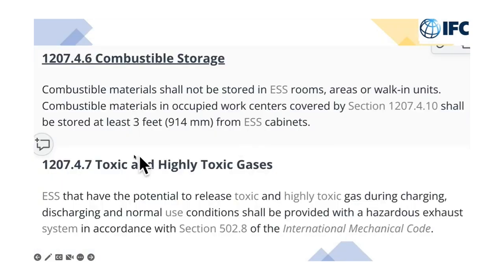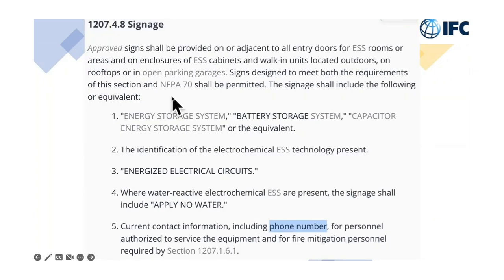Combustible storage, combustible materials. You don't store a can of gas in your energy storage room, of course. And we look out for toxic gases and things like that, hazardous systems. Some signage, and we have talked about signage in different places, just some different wordings that we have here. So if you are doing something that would comply with the IFC, like a commercial system, you might want to use this wording here. Energized electrical circuits, things like that, energy storage system, and the phone numbers.